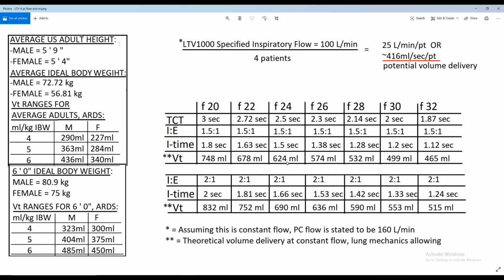That's if they were totally happy lungs that were happy to accept volume, which we know ARDS lungs are not. All that this is showing you is if the vent flowed at 100 liters per minute and was connected to 4 different patients, with these settings, what volume could you reasonably expect to be delivered to each patient? So that's what this double asterisk tidal volume down here is. It's the theoretical volume delivery at constant flow with the lung mechanics actually allowing that. So I know there's lots of things that factor into whether or not those lungs will actually allow that much gas to go in there.